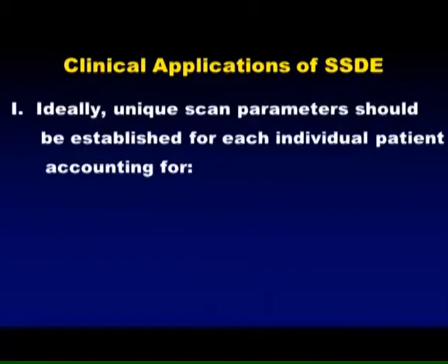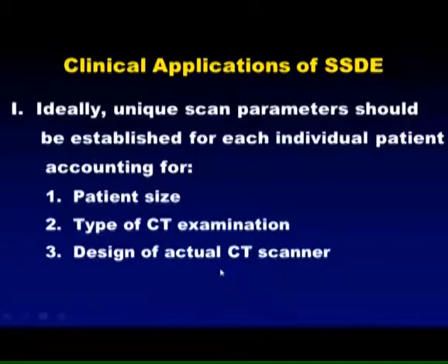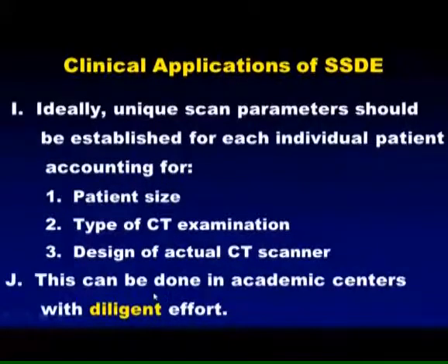So that's the foundation. Now, what can we do with SSDE that really makes a difference in the clinic? Well, if you went to the dose summit, you would have heard over and over that ideally unique scan parameters should be established for each individual patient, accounting for the patient's size, the CT examination type, and the design of the actual CT scanner. This can be done in academic centers with diligent effort. I have no quarrel with this approach.